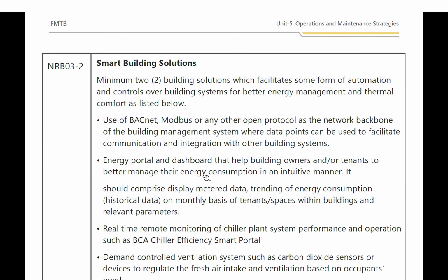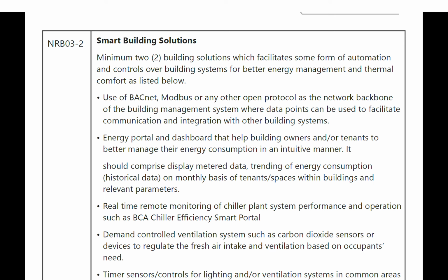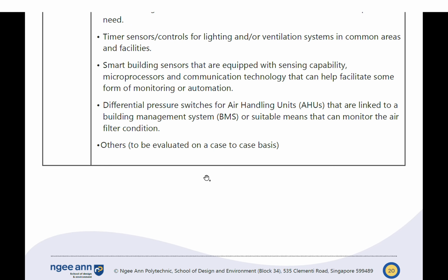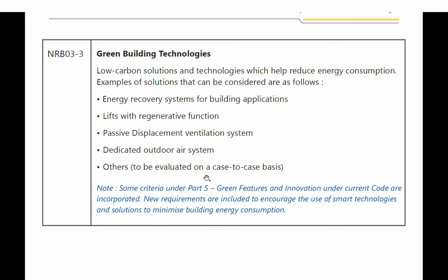Okay, smart building: we talk about smart solutions, better energy management in terms of thermal comfort, using BACnet or similar open protocols so that we can facilitate communication and integrate with other buildings. This is basically the whole idea. And then we talk about green building technology, right? Green building is basically a low carbon solution, a highly efficient building which can reduce energy consumption, through energy recovery, regenerative functions, and passive displacement ventilation, where you use cool air to cool the room itself, and also a dedicated outdoor air system. In thermodynamic terms, sometimes we use the enthalpy method to calculate the energy that is required, as part of green building technology.